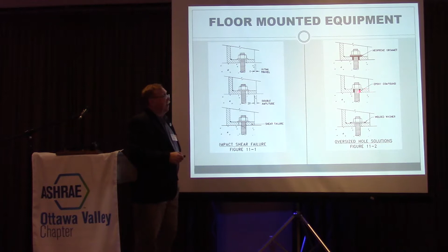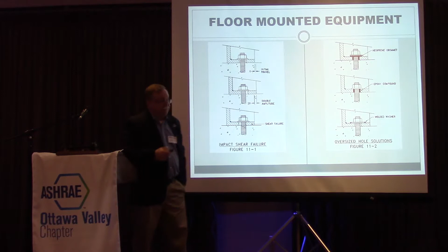3 very easy little things to do to avoid this. One, you put a rubber grommet in there so it can't move back and forth—the rubber grommet will actually de-accelerate the equipment as it starts to move. That's the basis for all seismic snubbers, having rubber inside them so it de-accelerates equipment as it's trying to move. You take epoxy compound—I'm just talking about adhesive anchor compound—squirt some in, put the washer on, bolt it down, you're done. Now you've filled up that gap, it can't bounce back and forth. Or you take the washer and tack weld it down. The average washer is 1/64 of an inch bigger than the bolt it's in, a 1/64 to a 32nd, somewhere in that area, so it can only move back and forth that small amount. 3 very easy, cheap fixes for saving equipment.